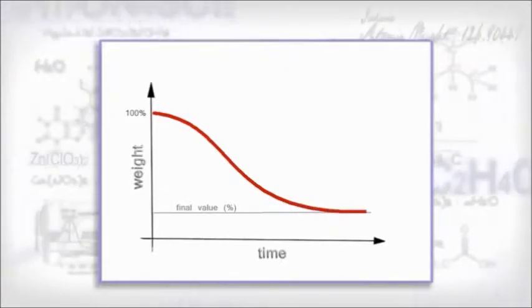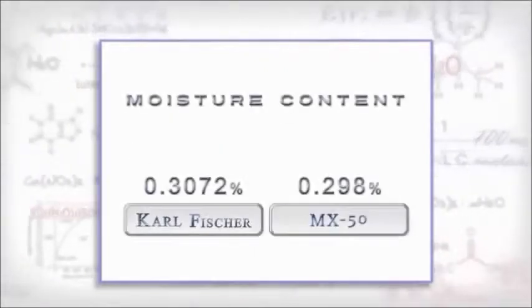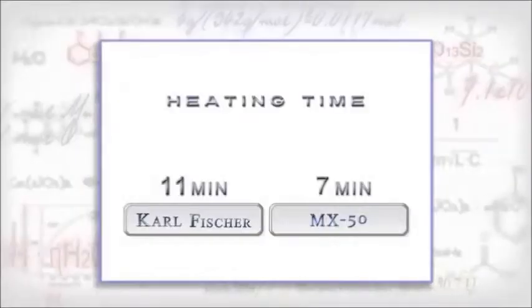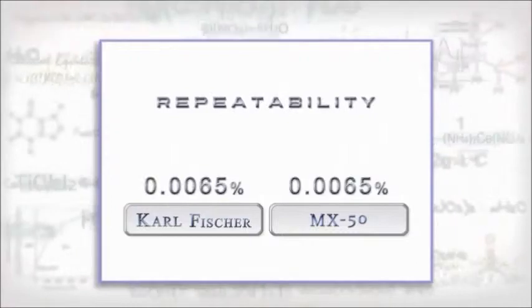A&D analyzers use the thermo-gravimetric or loss-on-drying principle and offer the accuracy of the Karl Fischer technique, but in less time and with better repeatability.